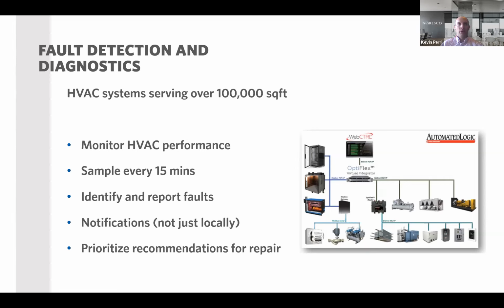to get ignored. So what the code has said we're going to do is not only do you do that on the local level, but you also must be capable of transmitting that fault to somebody located remotely. So sending a text message, sending an email, something of that nature has to be part of this fault detection and diagnostic system. So it's getting a little bit more in your face, if you will, on what is required on this, but it's really trying to catch the attention of people to address these items in a timely manner instead of just letting them carry on down the road until they get to it.